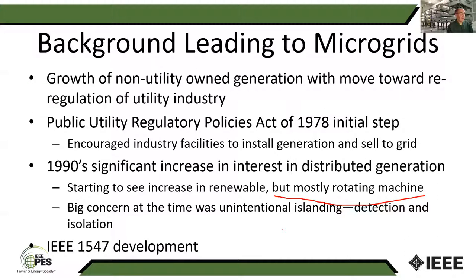It took a while to get this passed, and what they ended up doing is each time it went out for ballot, it got shorter and shorter. And then they put in 1547.1, .2, .3 for these substandards underneath it. And by then a lot of the interest and the hype had gone away, so they were able to pass these pieces. But this initial standard was very much an anti-islanding type of arrangement.